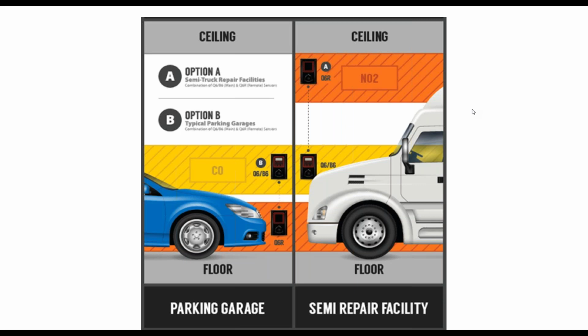The unique one that we run into once in a while is loading docks. The reason you may have to have your CO sensor and then an NO2 sensor high and maybe low is that these semis, depending on the type of truck, have an exhaust system that hits the floor. So you've got to have something low to the floor. But that doesn't exclude the ones that have the stacks that blow the NO2 up to the ceiling, and then it comes down, and if you put the NO2 sensor down at the bottom, that's a hazard and might run into problems. So that's why we recommend putting an NO2 sensor about 2 feet off the ceiling.